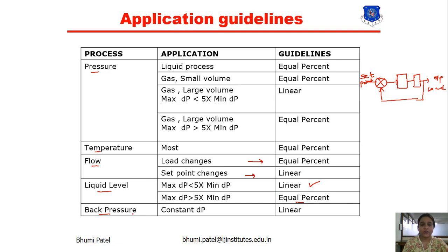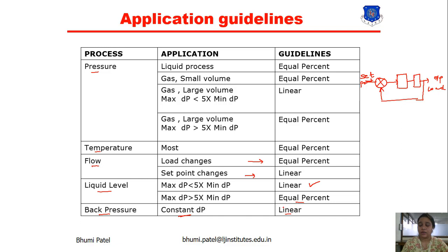For the back pressure process, when back pressure is generated in the process, we use constant differential pressure, and for that we compulsorily use linear characteristics. According to the application or output, we can decide the valve characteristic using this chart.